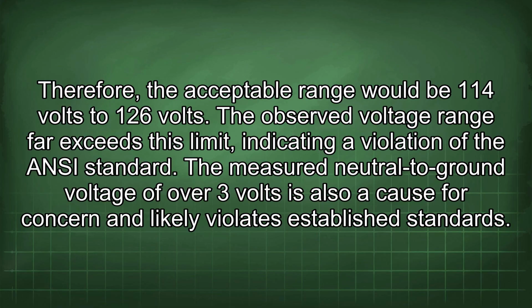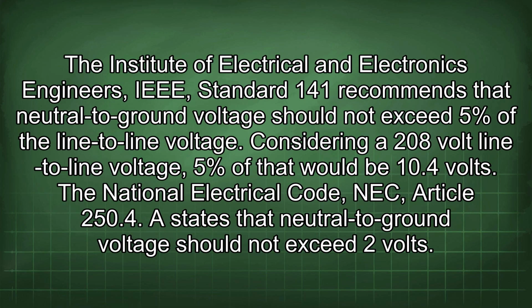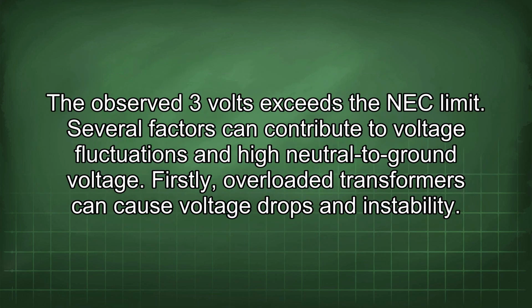The measured neutral to ground voltage of over 3 volts is also a cause for concern and likely violates established standards. The Institute of Electrical and Electronics Engineers, IEEE Standard 141, recommends that neutral to ground voltage should not exceed 5% of the line-to-line voltage. Considering a 208-volt line-to-line voltage, 5% of that would be 10.4 volts. The National Electrical Code, NEC Article 250.4, states that neutral to ground voltage should not exceed 2 volts. The observed 3 volts exceeds the NEC limit.